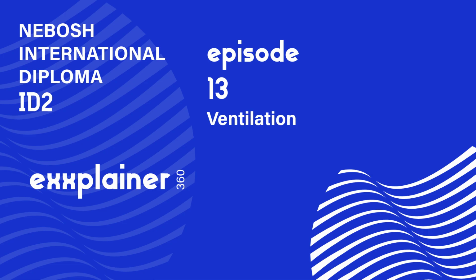Stage 1 is pretty straightforward. A visual inspection. Just looking around. Basically, yes. But looking with a trained eye. Are there obvious signs of damage? Dents in the ductwork. Is dust settling around the hood opening, suggesting it's not capturing properly? What else? Broken seals. Is the fan making excessive noise or vibrating badly? Things like worn fan belts. You can often spot problems just by looking and listening carefully before you even get any instruments out.